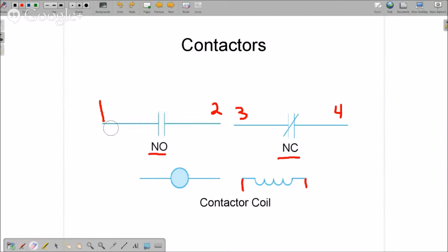Here's where it gets difficult: schematic diagrams always show contactors and relays in their resting position, which means no power applied. But when you flip the thermostat on and it supplies power to this coil, the normally open contact switch closes and the normally closed contact switch opens. You can't see that on the schematic diagram, so you have to know - do I have power at the coil of the contactor? If yes, then mentally you have to close that normally open switch and open the normally closed switch.